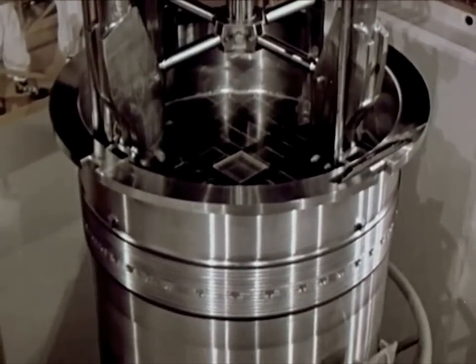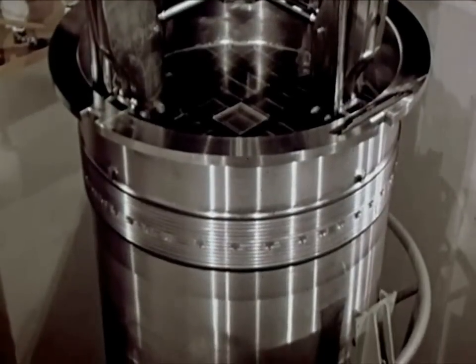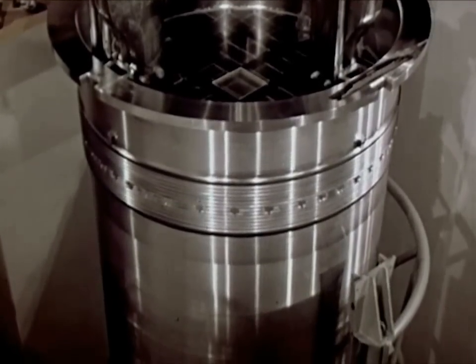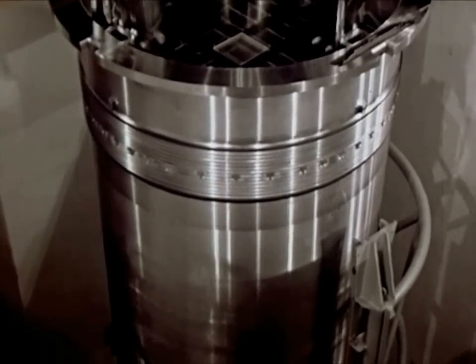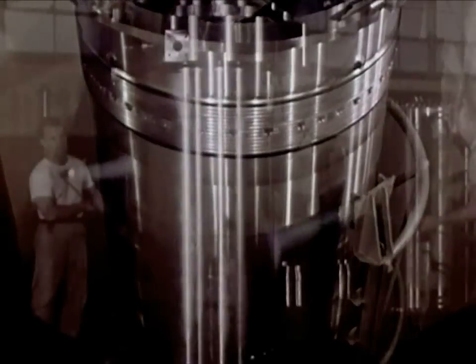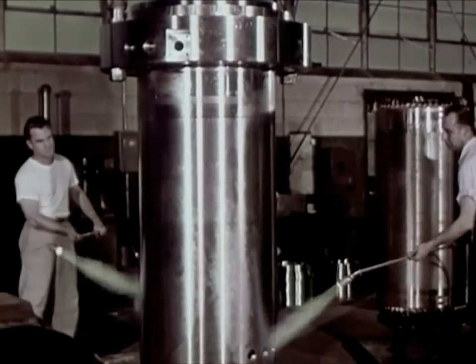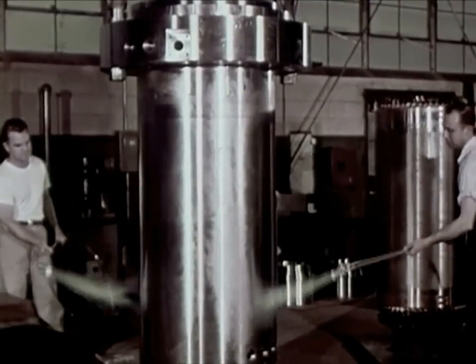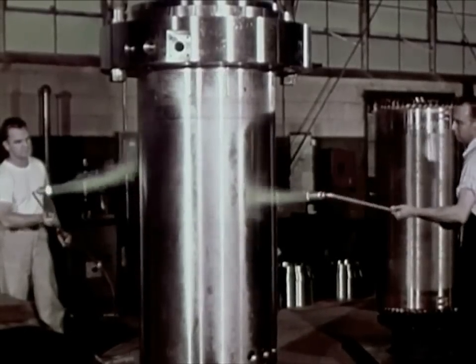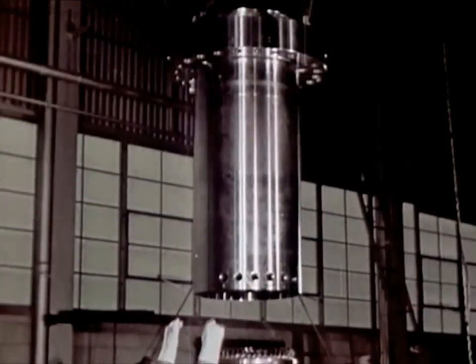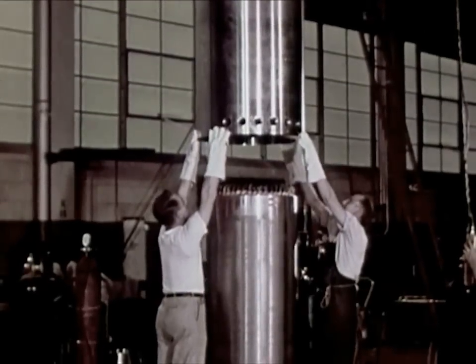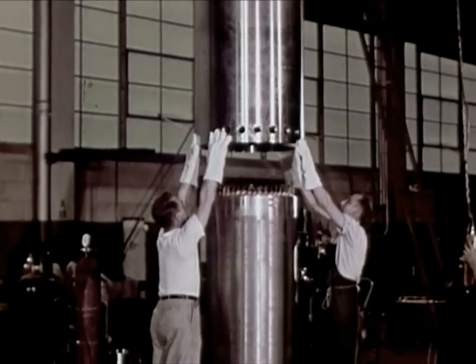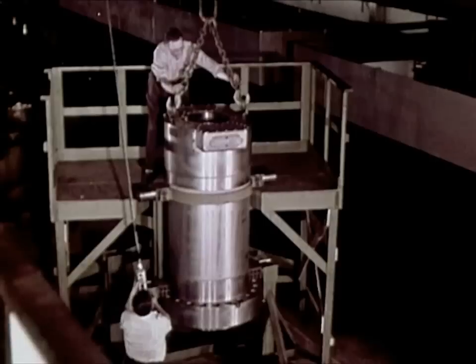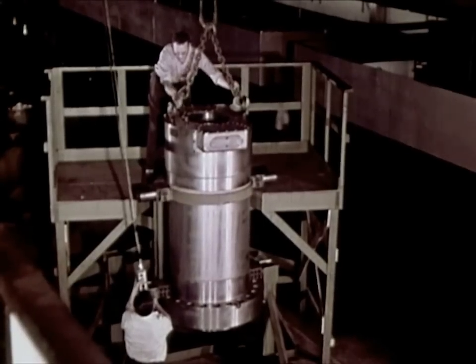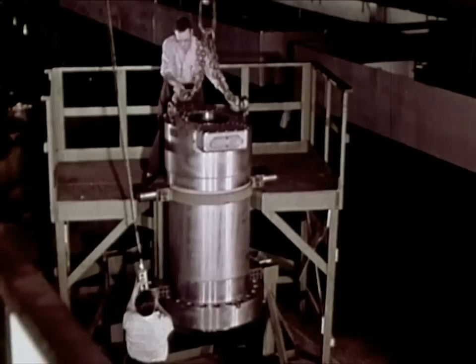The Shippingport plant has a large number of newly developed items of equipment to ensure safety and reliability. Typical of these are zero leakage canned motor pumps. In this design, no shaft seal is necessary. Metal cans enclose both stator and rotor. Primary water circulates between them, lubricating the bearings and cooling the induction motor. A separate water supply cools the stator coils.